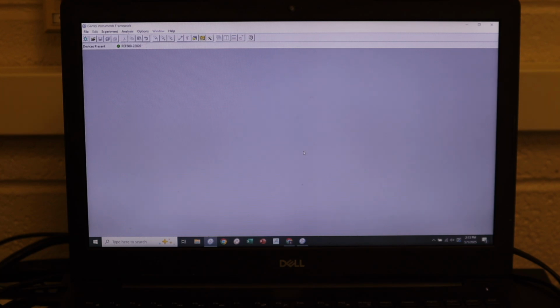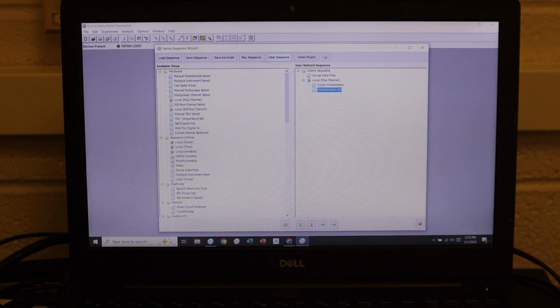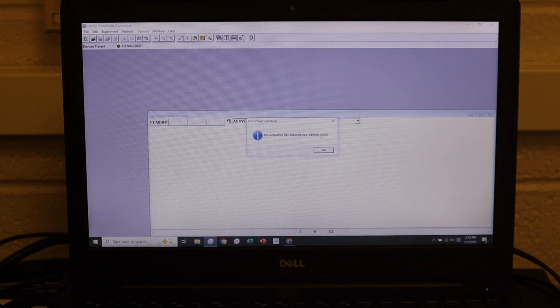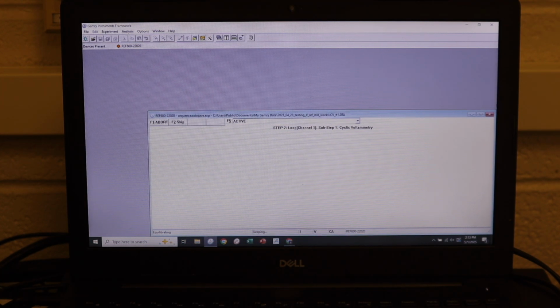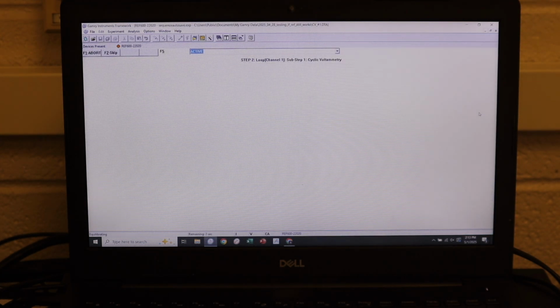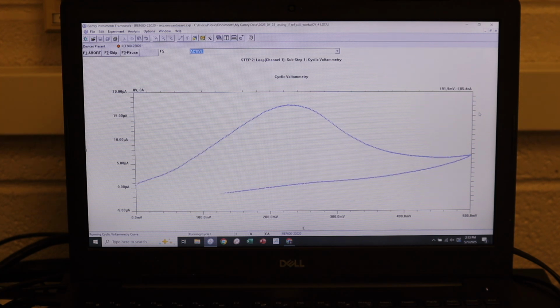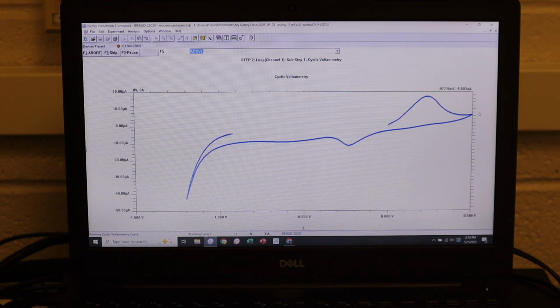So we can go ahead and hit OK. Now something that I always like to do after calibrating is run a little experiment to make sure that our device data looks nice, like we would expect. So we're going to go ahead and run our electrochemical impedance spectroscopy and cyclic voltammetry on a contact to make sure that we see really clean and clear signals both in our CVs and in our EIS. Again, it's just asking us if we want to replace the data, which we do. We can go full screen and we'll start out with a cyclic voltammetry scan. Right now we're doing our measurements, like all of our measurements, in 1x phosphate buffered saline. This is a gold electrode contact, and this is the cyclic voltammetry scan.